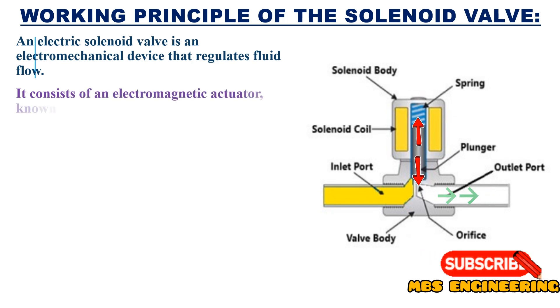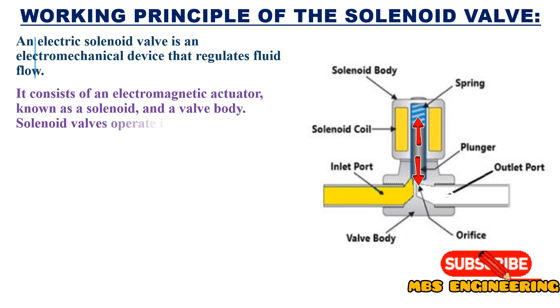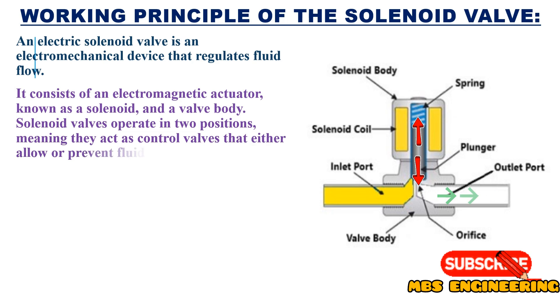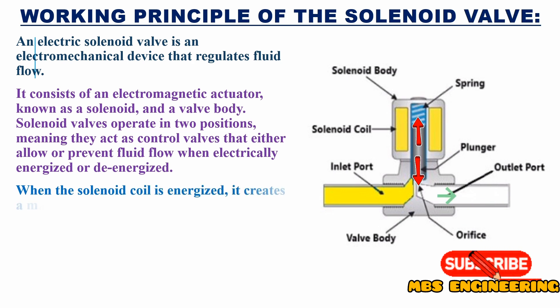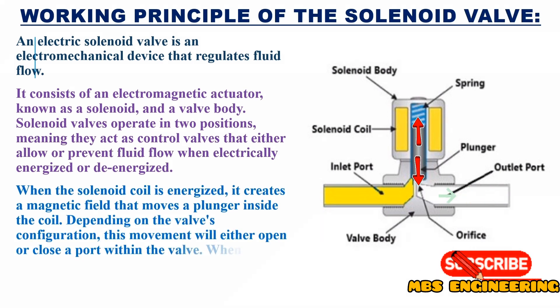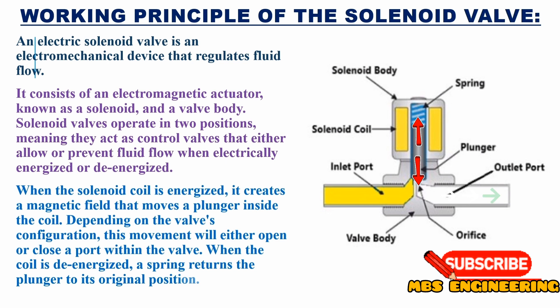Next, we will understand the working principle of the solenoid valve. An electric solenoid valve is an electromechanical device that regulates fluid flow. It consists of an electromagnetic actuator known as a solenoid and a valve body. Solenoid valves operate in two positions, acting as control valves that either allow or prevent fluid flow when electrically energized or de-energized. When the solenoid coil is energized, it creates a magnetic field that moves a plunger inside the coil. Depending on the valve's configuration, this movement will either open or close a port within the valve. When the coil is de-energized, a spring returns the plunger to its original position.